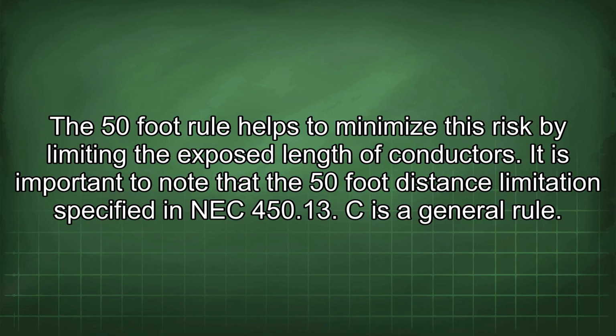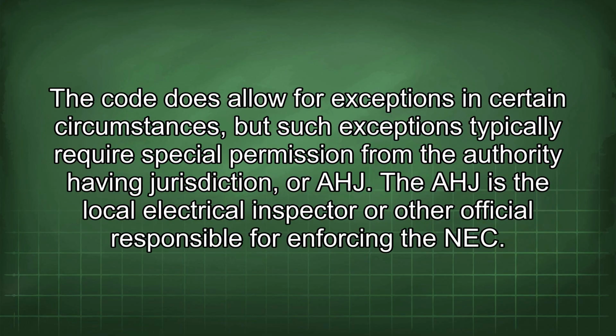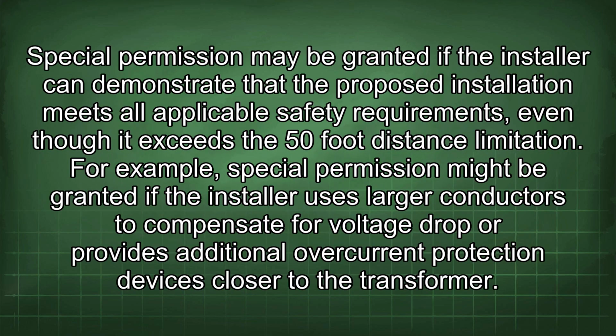It is important to note that the 50-foot distance limitation specified in NEC 450.13 C is a general rule. The code does allow for exceptions in certain circumstances, but such exceptions typically require special permission from the authority having jurisdiction, or AHJ. The AHJ is the local electrical inspector or other official responsible for enforcing the NEC. Special permission may be granted if the installer can demonstrate that the proposed installation meets all applicable safety requirements, even though it exceeds the 50-foot distance limitation.